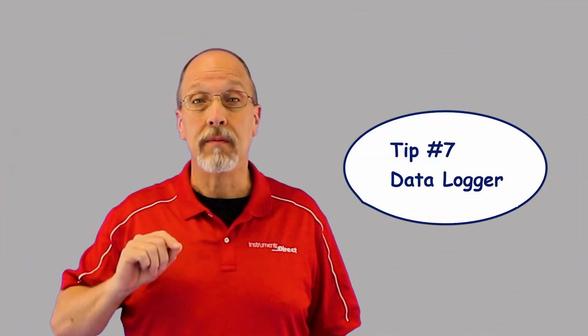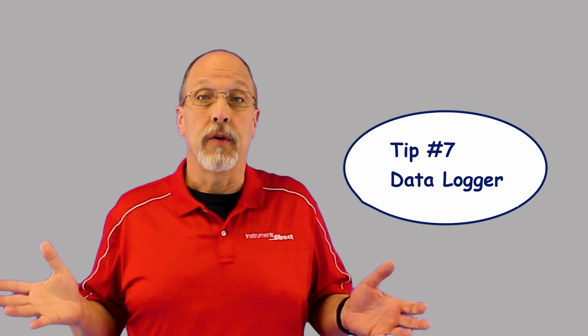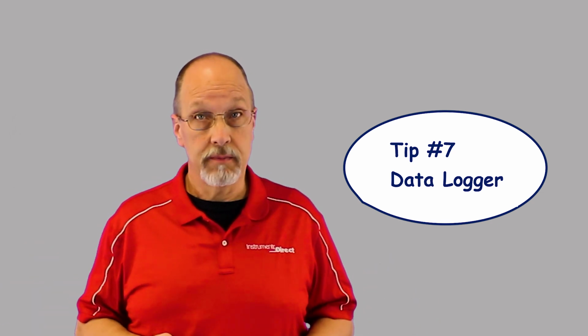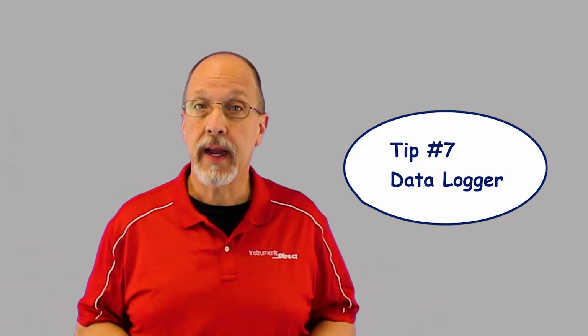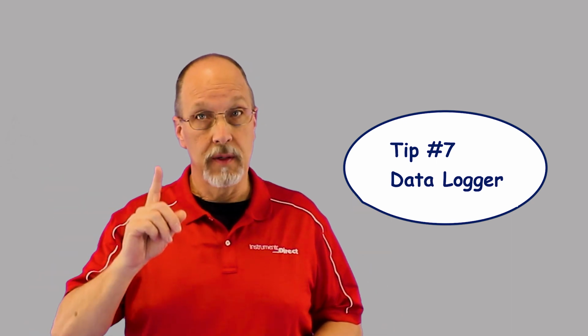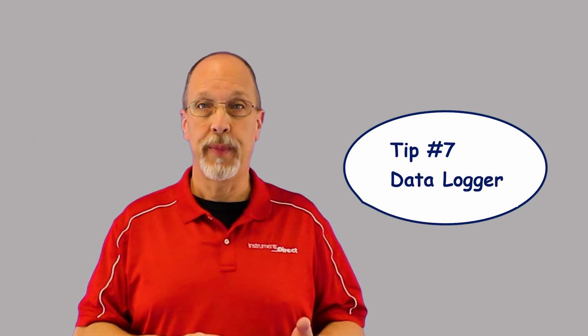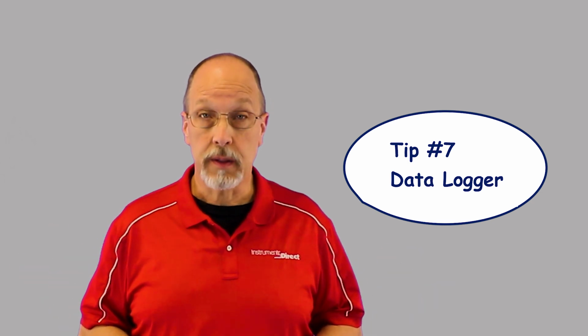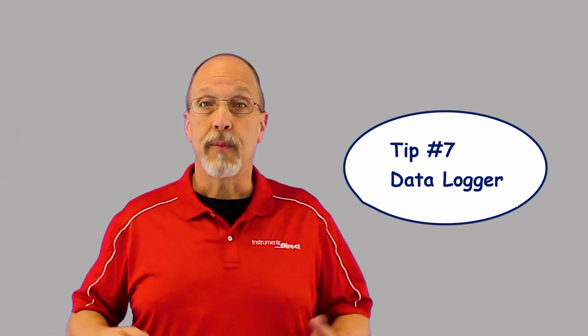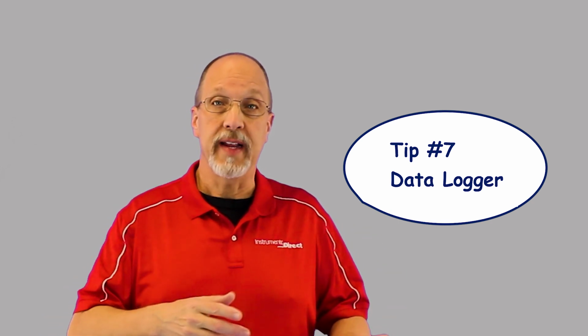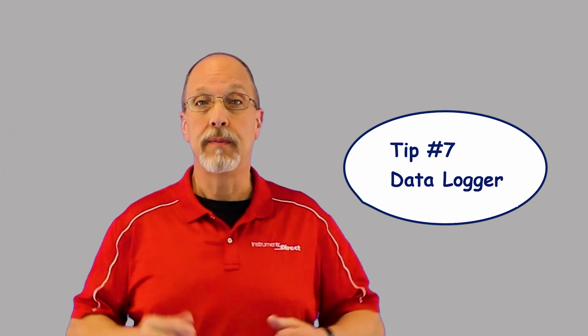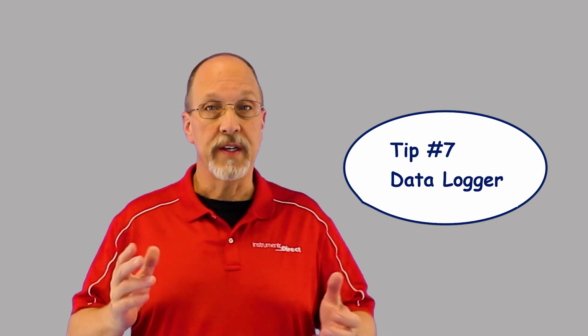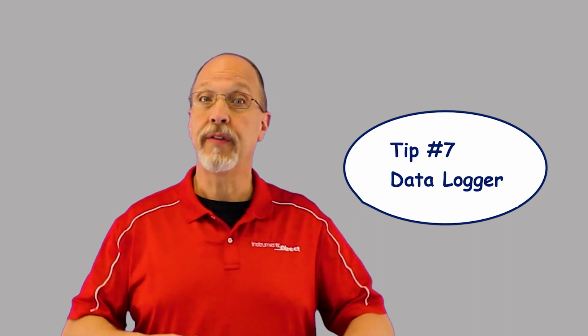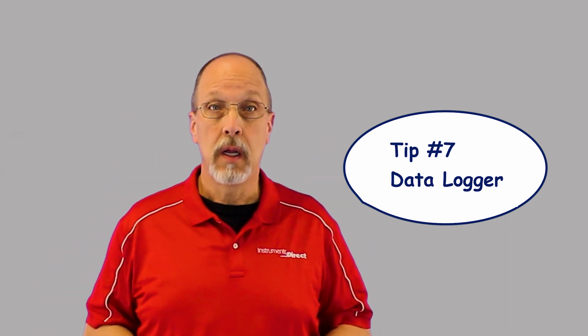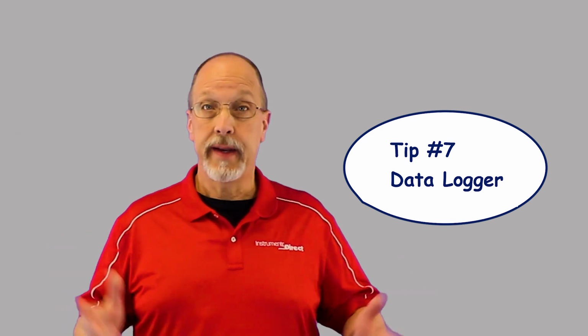Tip number 7, the data logger. If you're leaving your flow meter behind for a flow study, in some cases you can just reset the totalizer and you're done with it. However, if you'd like to log your flow rate, your total, even your temperature or BTU for energy, you'll need to fire up the old data logger for sure. Now, to program it, you need to start off with your start and stop time and how often you like to take a sample. Well, most people use once a minute sample rate, which adds up to 1,440 data points in a day. Over a week or more, that's a lot of data.